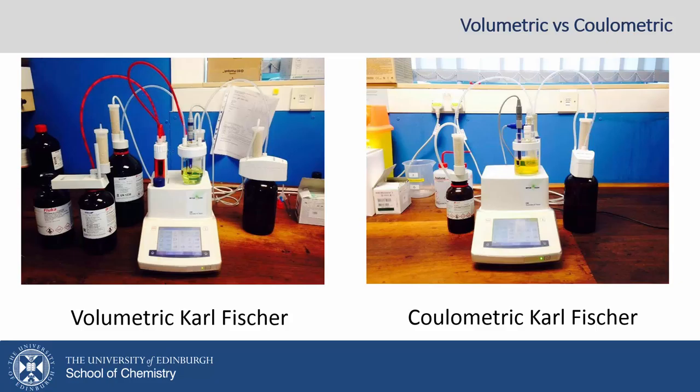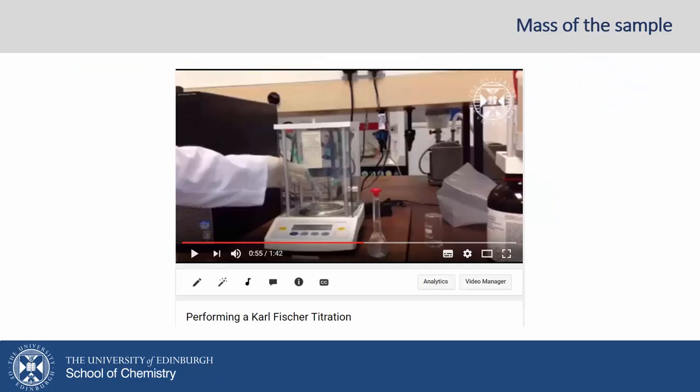For coulometric titrations, iodine is generated in situ from iodide ions, producing iodine which reacts with water. This continues until all the water is used up. This approach — the generation of iodine in small amounts — means that it can be used for analysis of samples with a much smaller amount of water present.